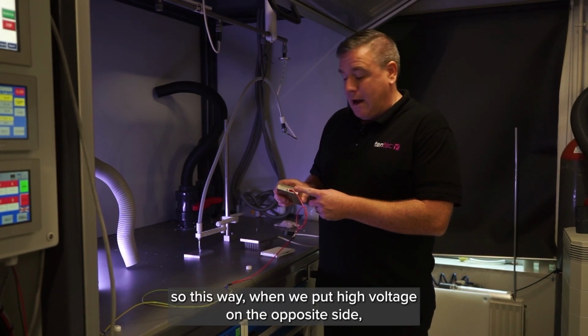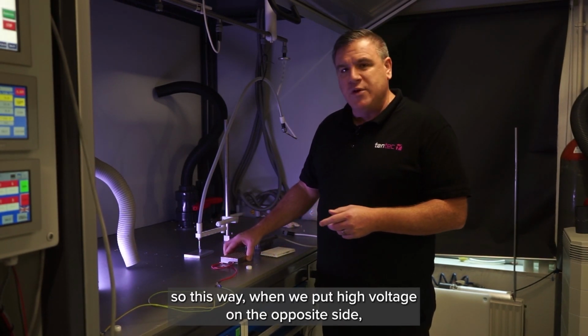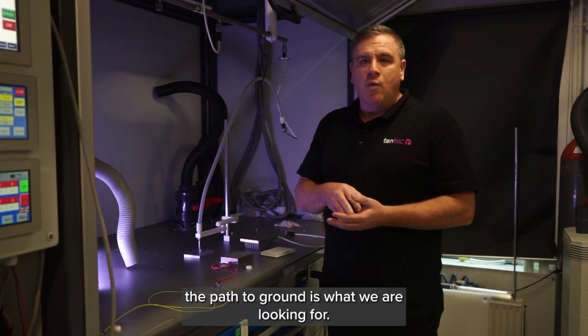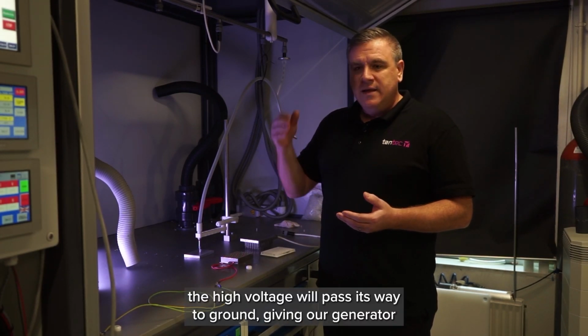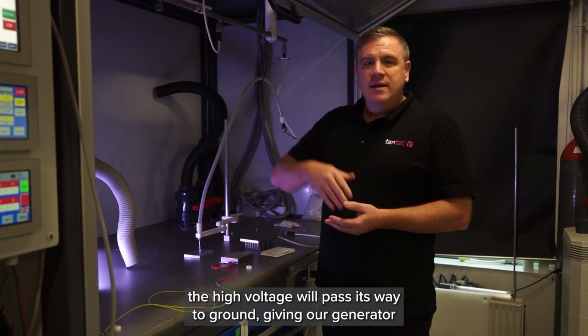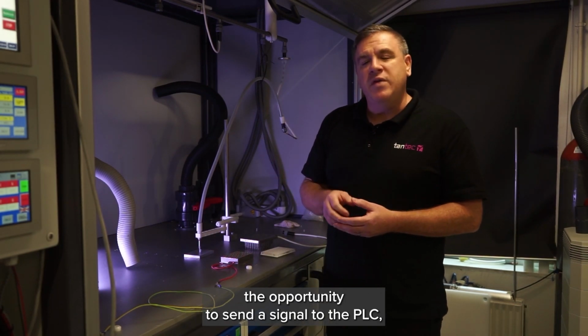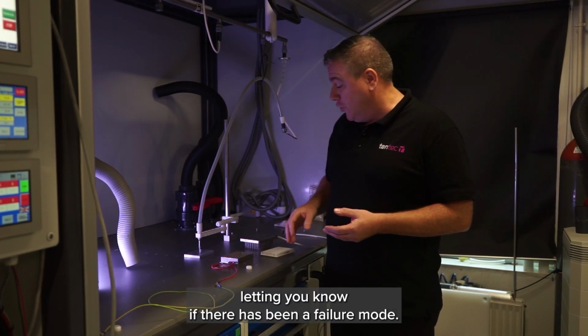This is grounded out. So this way, when we put high voltage on the opposite side, the path to ground is what we're looking for. So if a hole is present, the high voltage will pass its way to ground, giving our generator the opportunity to send a signal to the PLC, letting you know that there's been a failure mode.